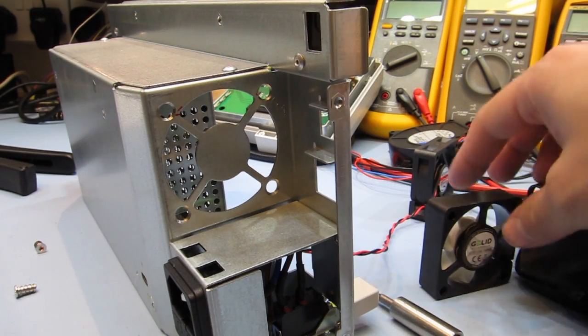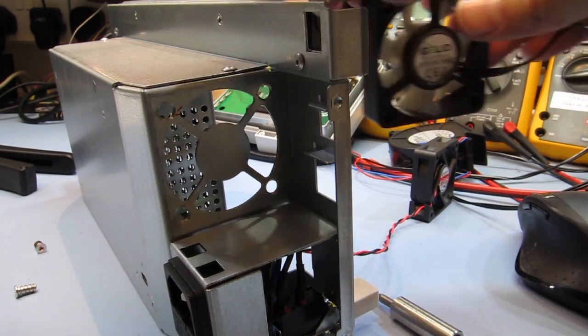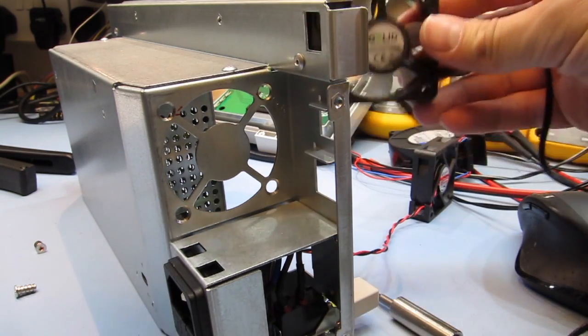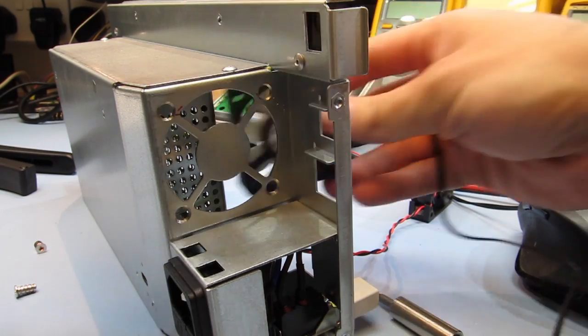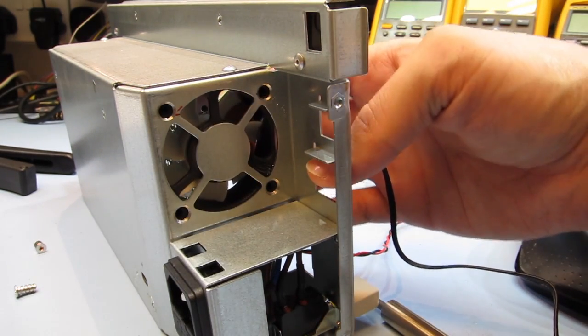For any of you also installing a new fan, you just want to make sure that the airflow is blowing through the casework in this direction. So generally that's with the label facing towards the outside of the case.